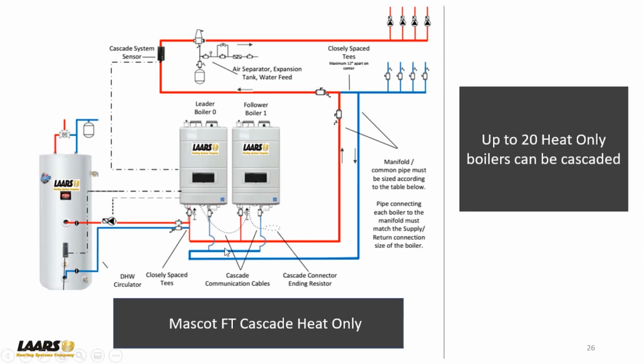Now, here I'm showing, and I mentioned earlier that we can cascade up to 20 heating-only boilers. So very simply here, we've got 2 heating-only cascaded. We have a system loop, and here we're showing zone pumping, okay? 2 closely spaced T's. There's my primary, secondary. So here's our boiler loop as primary, okay?